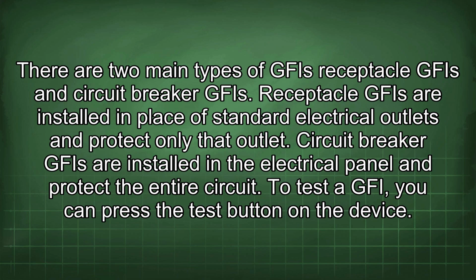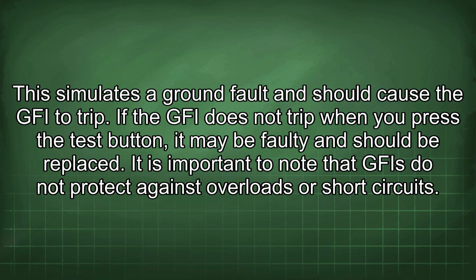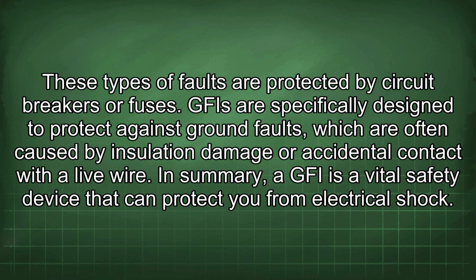To test a GFI, you can press the test button on the device. This simulates a ground fault and should cause the GFI to trip. If the GFI does not trip when you press the test button, it may be faulty and should be replaced. It is important to note that GFI do not protect against overload or short circuits. These types of faults are protected by circuit breakers or fuses.